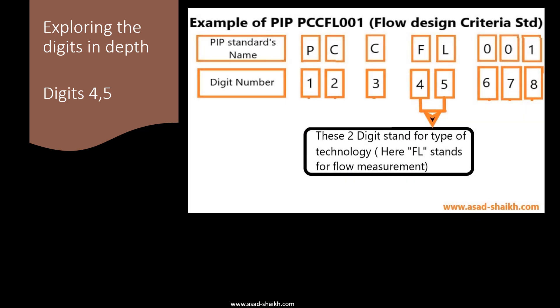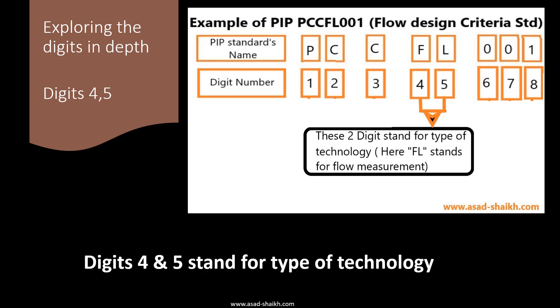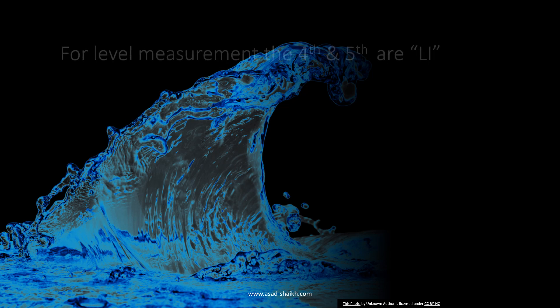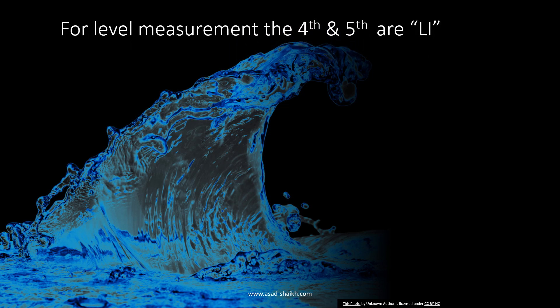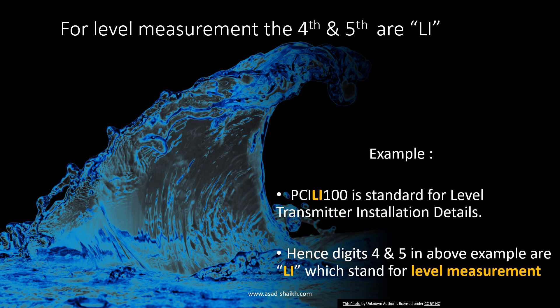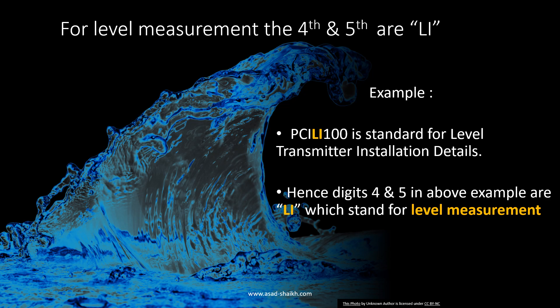Digits four and five are straightforward — they stand for the type of technology used. In our example, it was flow meter technology, so digits four and five are FL. For level measurement technology, they would be LI. Taking another example: PCILI — here PC is the instrumentation department, I means installation detail, and LI indicates it caters to level measurement technology.